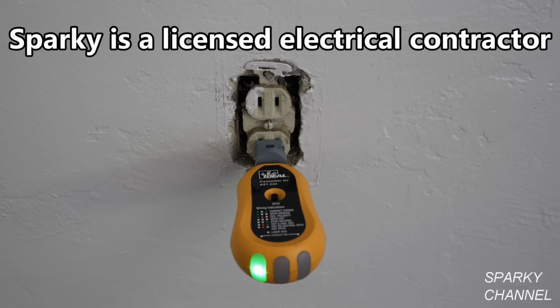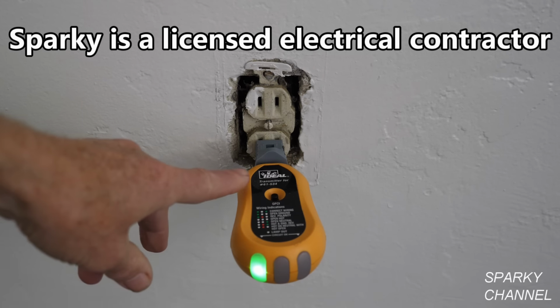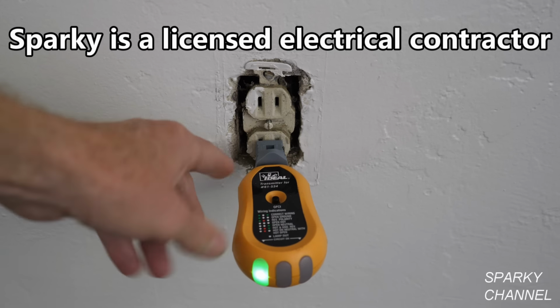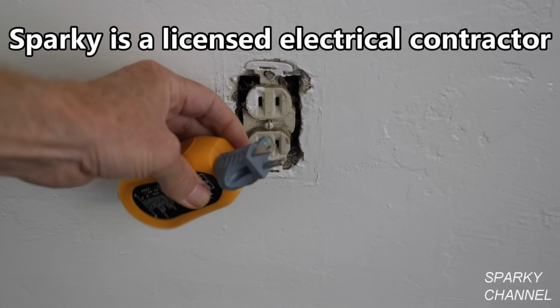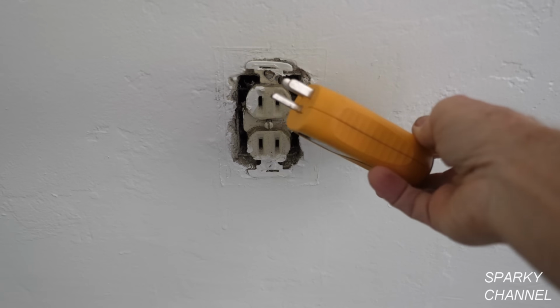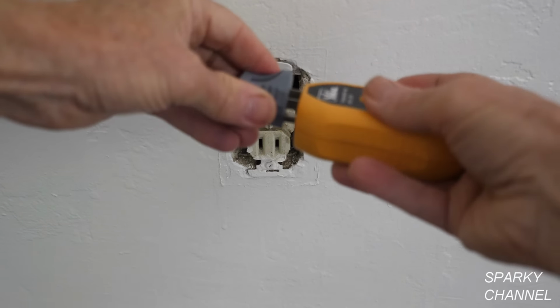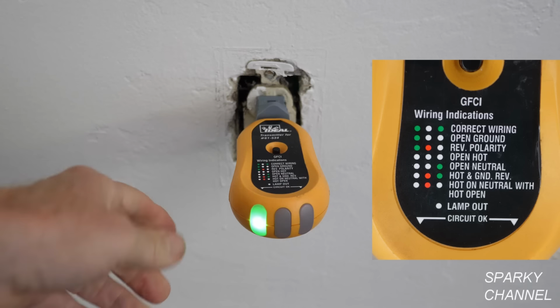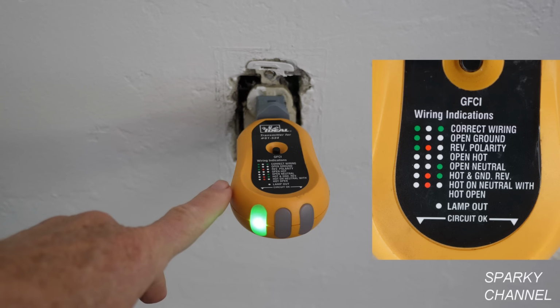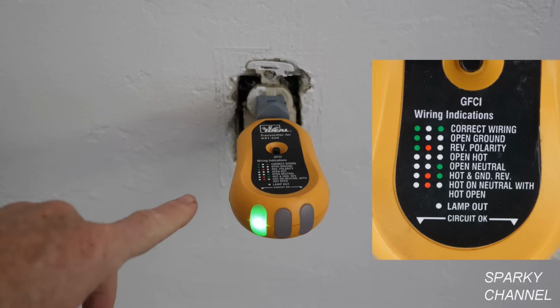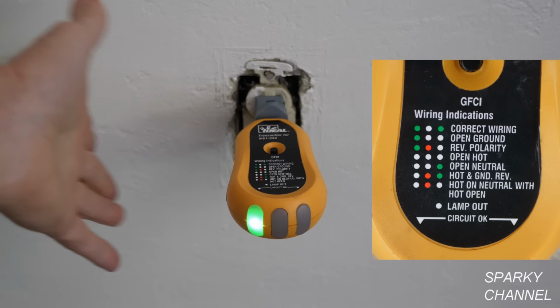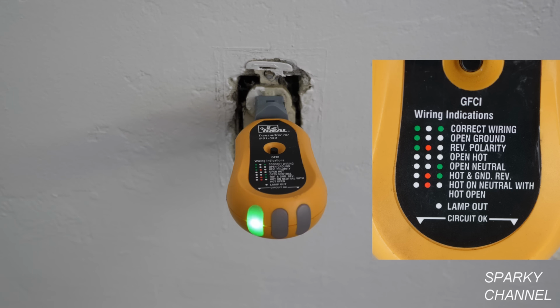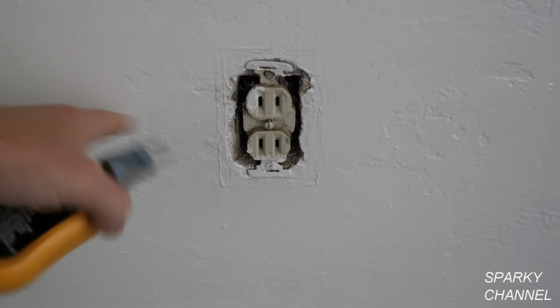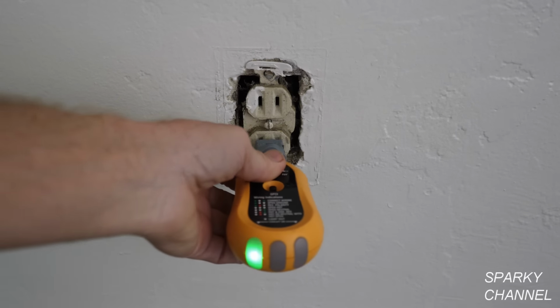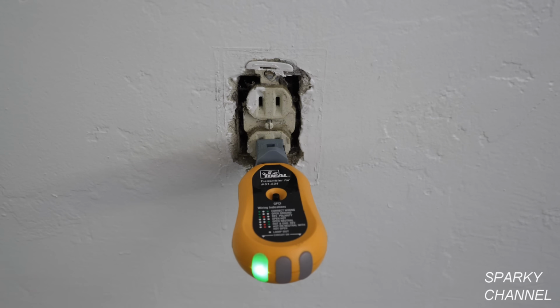And the first thing I've done here is I've plugged in my Ideal transmitter. You see, I actually have an adapter on it. This one comes with 3 prongs, but if you just put a little adapter on it and plug it in, it'll give you the correct reading. This reading means open ground. Right here, that's what this means, open ground, which you would expect because this is an old 2-prong ungrounded receptacle. So you plug that in, it says open ground.